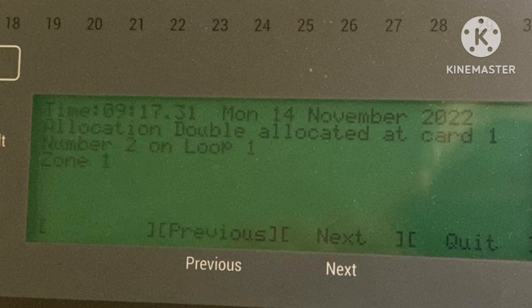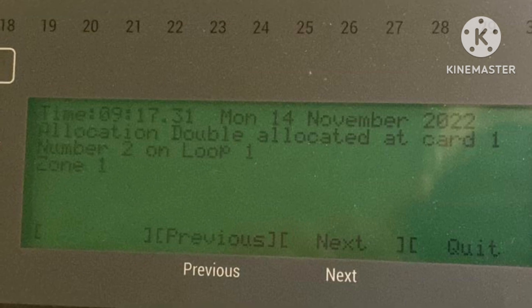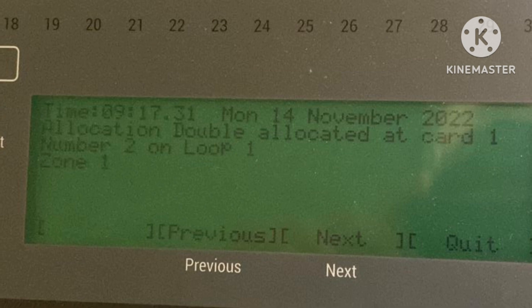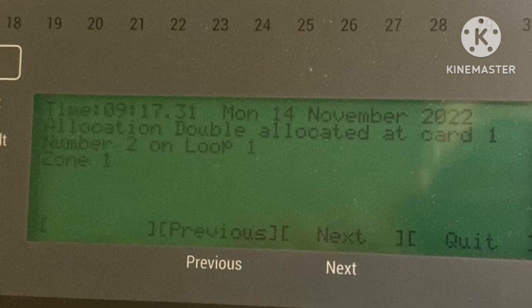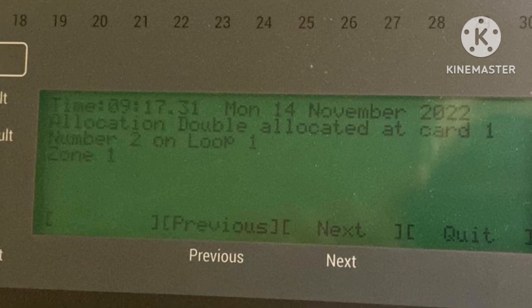The fault message looks like this: 'Allocation double allocated at card 1, number 2, on loop 1.' This appears according to card and device number and loop card. This fault is related to the power loop card — it means that two devices have been given the same address, or there may be a bad connection on that device, or the device itself is faulty.